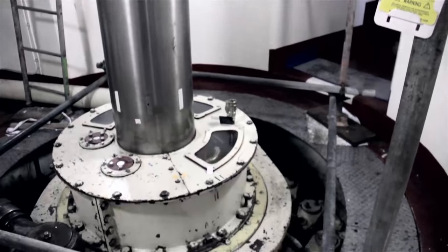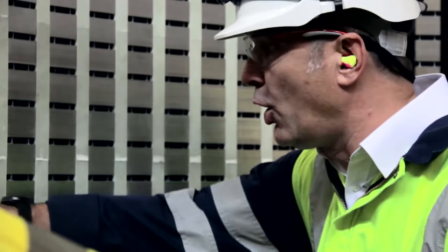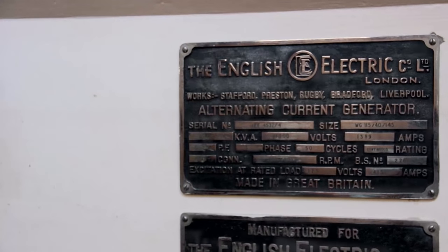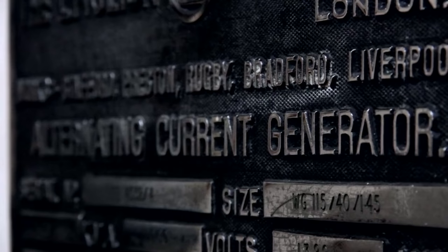Back in 2012 we carried out an overhaul on the station due to some high vibration that was detected. The investigation centred around an issue with the stator core. This machine was built 70 years ago in two halves — they manufactured two windings in the factory, brought them up to the station, and joined them together. Over the years during service, this has created a lot of vibration.